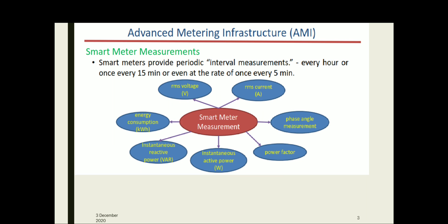A smart meter provides periodic interval measurements — every hour, every 15 minutes, or even every 5 minutes — measuring various parameters and transmitting these values to the meter data management system. A smart meter can measure RMS voltage, RMS current, phase angle, power factor, instantaneous active power, reactive power, energy consumption, etc. All these values can be stored as a repository in the meter data management system.